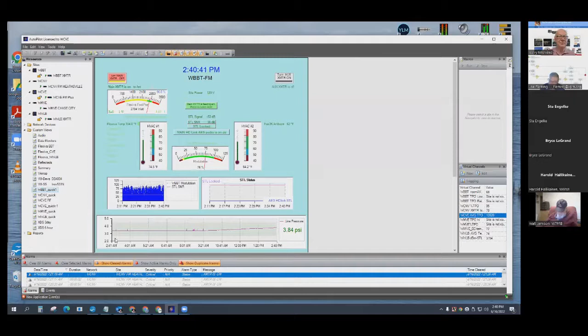That little section we saw in the middle becomes a highlighted zone showing our ideal area. I've got it marked for that site at about 2.5, 2 3/4 to 4.5 pounds of pressure in my 1 5/8 line. It does these weird little bumps I've never figured out, but overall I'm running around 3.5, and pressure started to increase here. My guess would be that our dehydrator kicked on and brought the pressure up a bit, then held it steady.